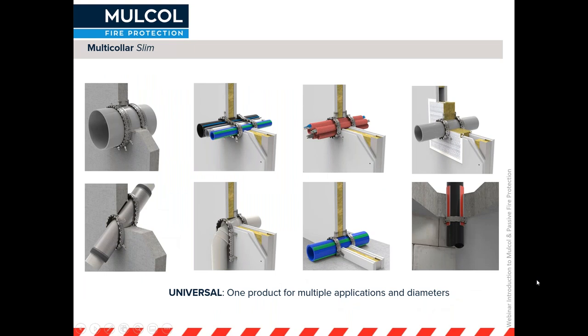Here are some more applications. For example, a 315 millimeter PVC pipe, but also inclined pipes, and we have now tested it with our coated board system as well, because we realized that often you've just got a big opening and you need to put a coated board in. So for inclined pipes, either with or without acoustic insulation, elbow pipes, but also pipes in what I would say are tricky situations where you can't put a full collar around them because they are too close to the floor or too close to a corner, we have tested these applications where you can still achieve your fire rating, even though you can't physically put a full collar around them. So it's a universal collar for many different applications.